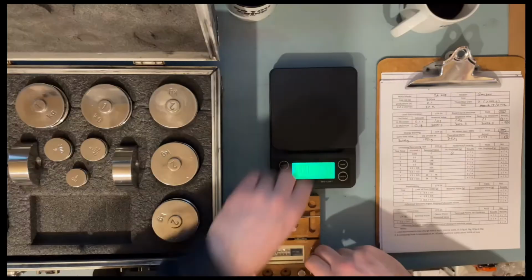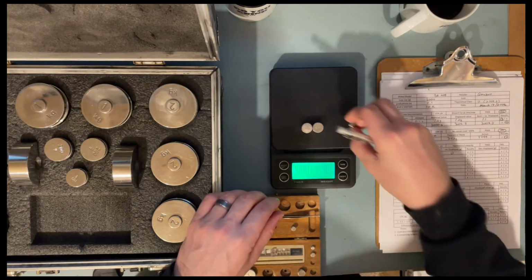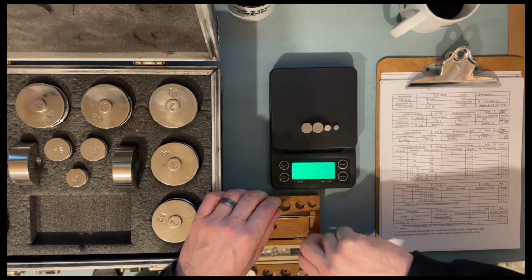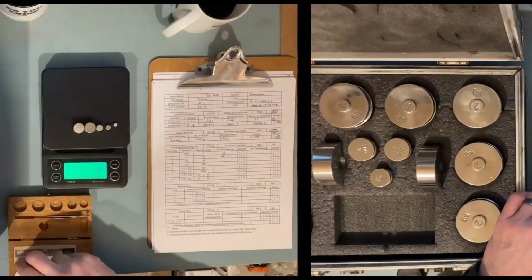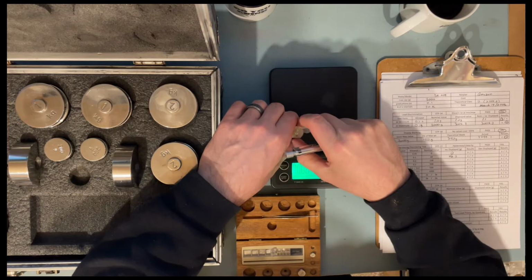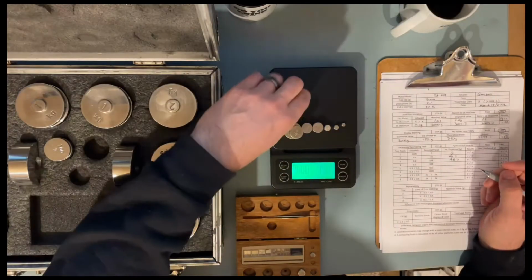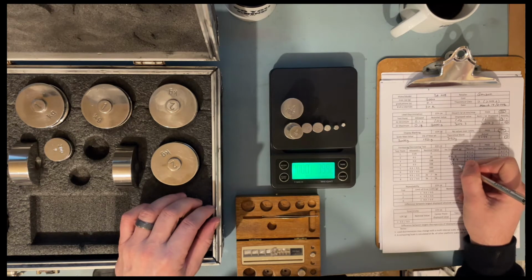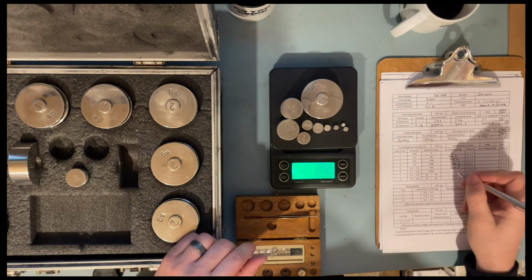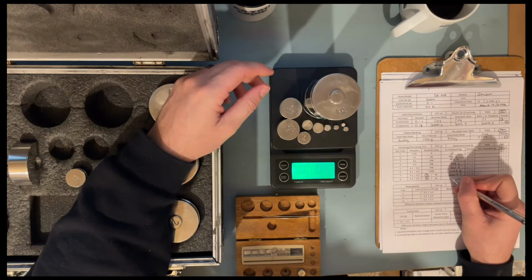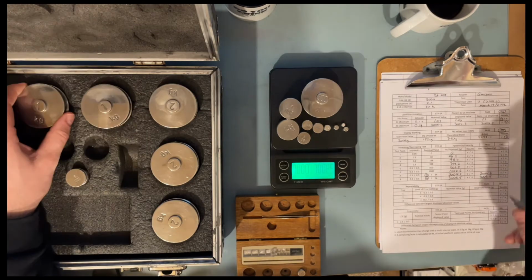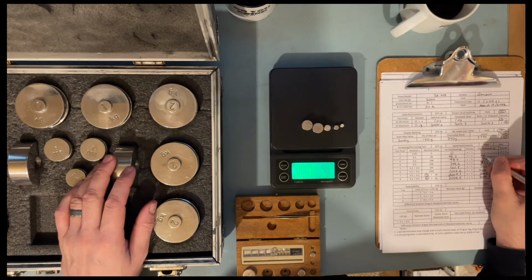The next test we do is called increasing decreasing. The increasing decreasing test is where we take points called critical test points where the limit of error is increased, and we want to ensure that the scale is within tolerances at those points. We start at 0, go up to maximum, making a point to hit all those critical test points, and then we do from the top back down to the bottom again. For increasing decreasing, this scale fails.